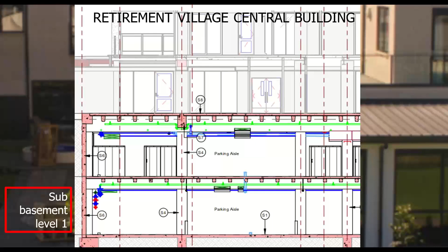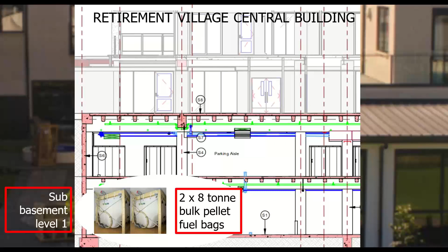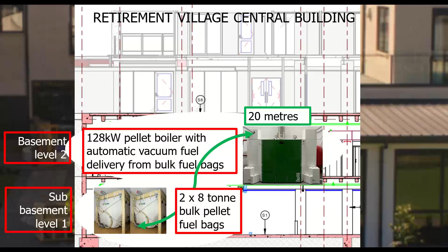We've got an 8-story building, including the two basement levels. In sub-basement level 1, there'll be a couple of these 8-ton bulk store flexi silo pellet stores. And then in basement level 2, there'll be a 130 kilowatt pellet boiler with automatic transfer between the two. That's about 20 meters away and about 4 meters of elevation or so.